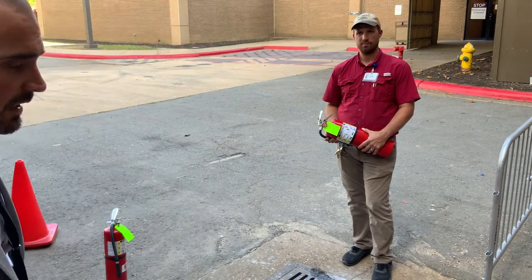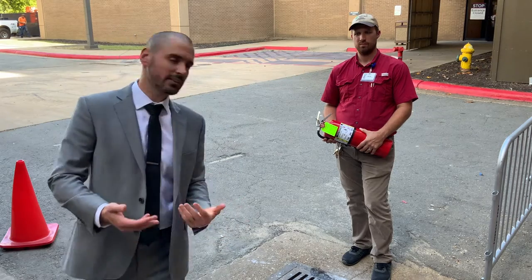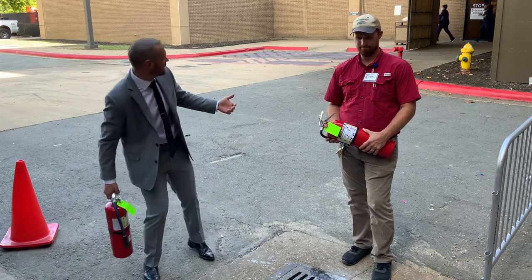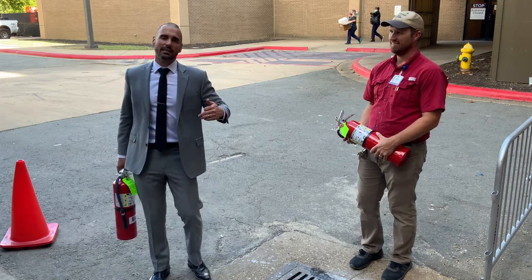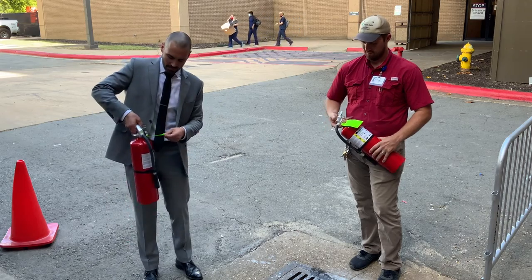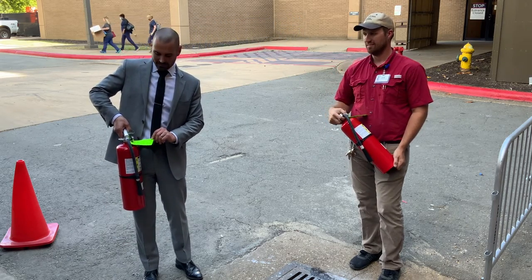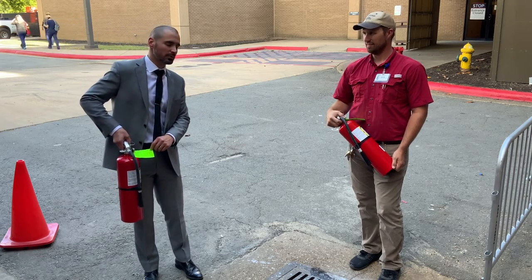It had 36 signatures. So that's a great indication that when you hit that 12, it's time to do your annual. Something else that we actually got a call on today for a different facility was that a fire marshal kindly helped us figure out that the inspector from last year for the annual accidentally did punch the wrong year for two of our extinguishers.